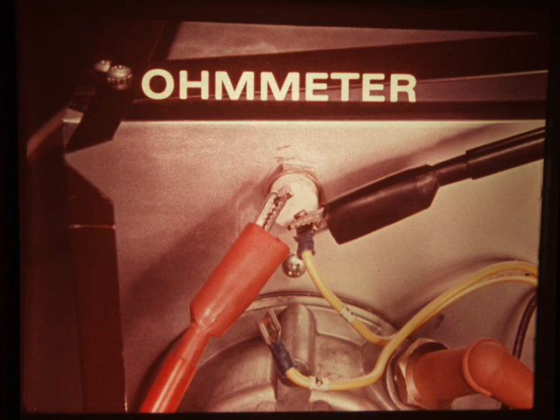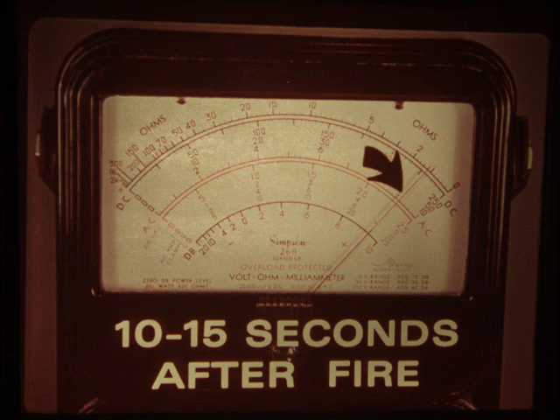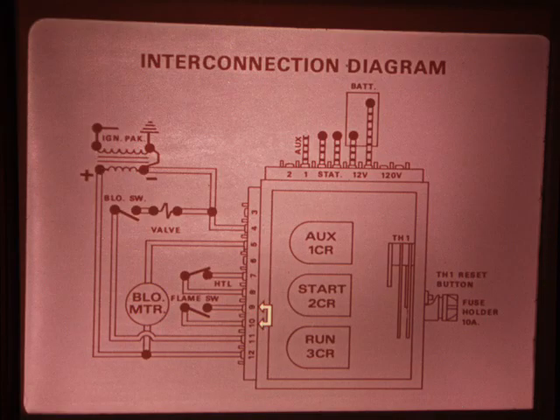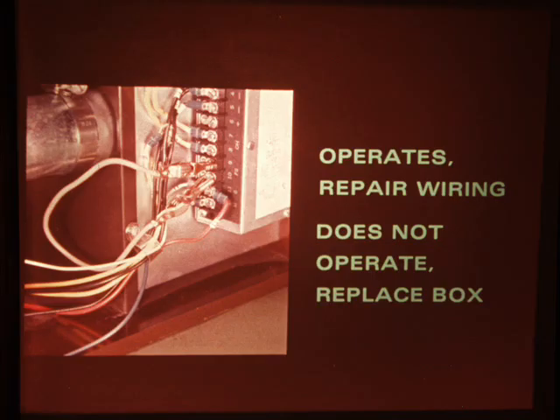Remove wire number 9 at the flame rod switch and connect an ohmmeter across the terminals. Turn on the thermostat. The resistance of the flame rod switch should go to about 0 ohms within 10 to 15 seconds after the furnace fires. If it doesn't, replace the flame rod. If the flame rod checks OK, jump terminals 9 and 10 on the control box to bypass the flame rod circuit and see if the box is all right. If the furnace operates OK with the terminals jumped, it means the flame rod wiring is defective and you'll have to repair it. If not, replace the control box. That's how to solve reset popping problems.